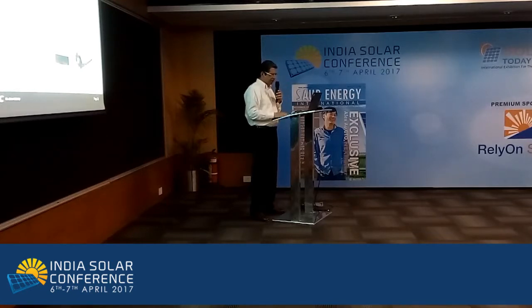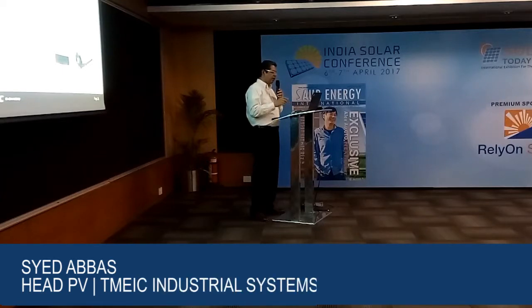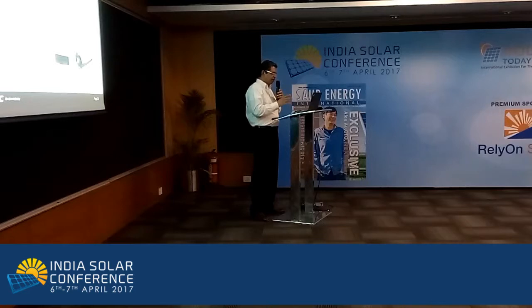We have done maybe more than 350,000 IGBTs in the field now, and the failures are none, or maybe one or two if at all. The reason is the junction temperature to which Mitsubishi Electric have designed their IGBT is 150 degrees centigrade. And because of the 3-level switching I just talked about, the maximum temperature you come across on the junction is 52 degrees centigrade. Therefore, the stress on the component itself is so low that you don't have any failures. It's not rocket science, it's just that they have packed so much into that junction itself.